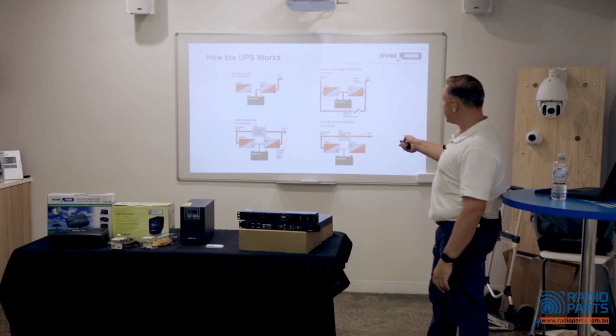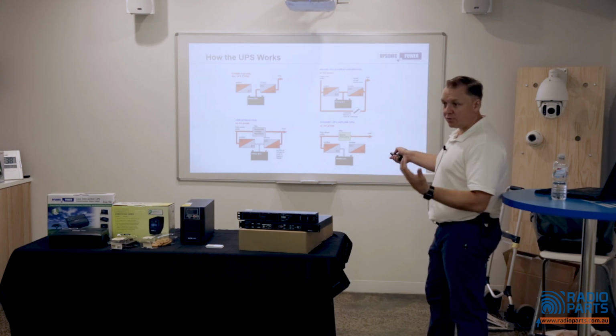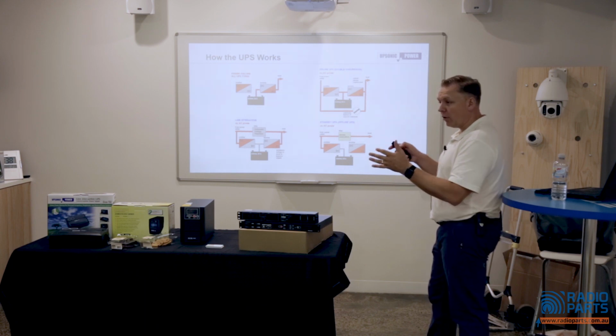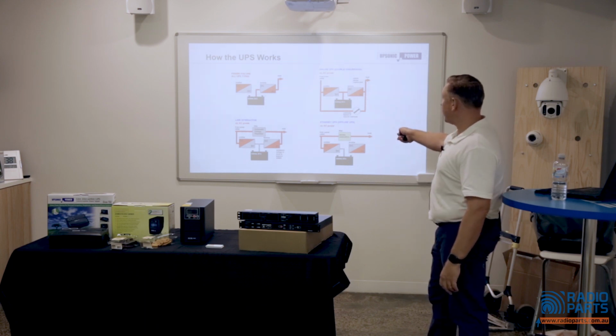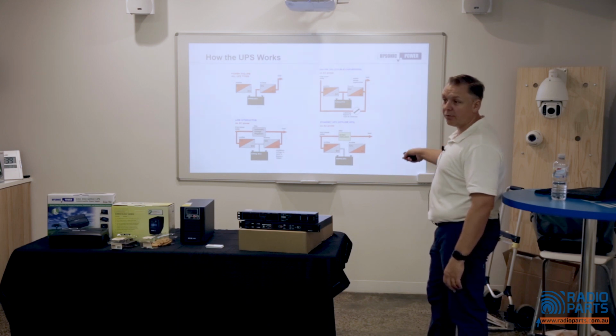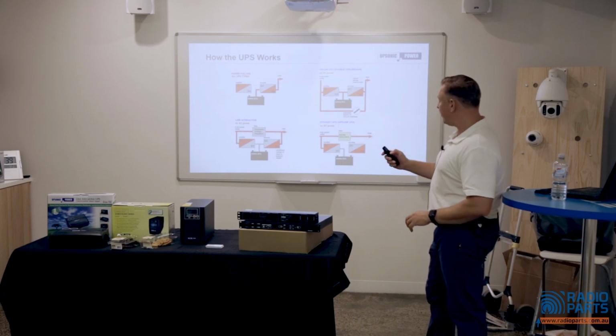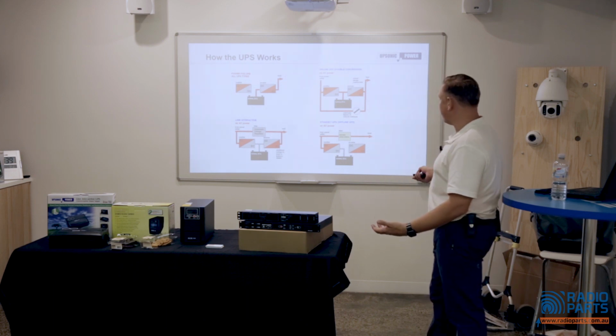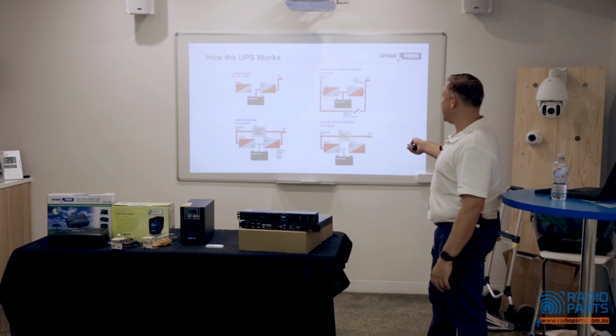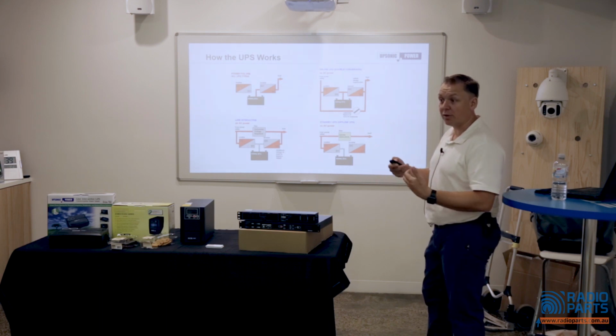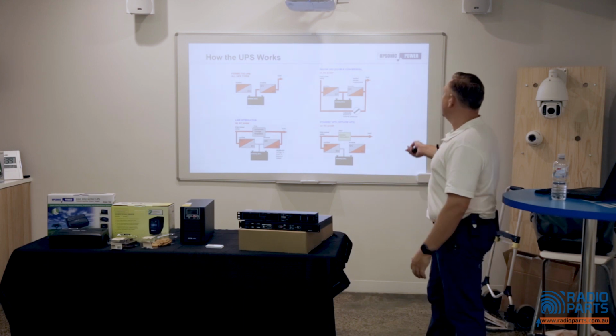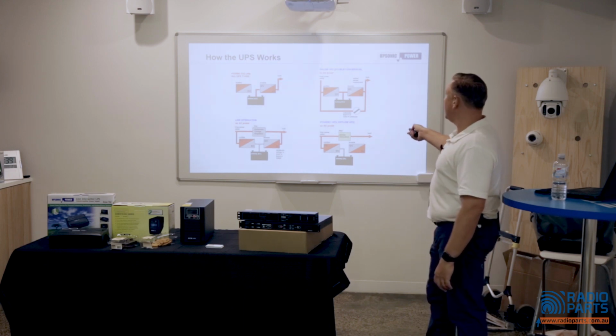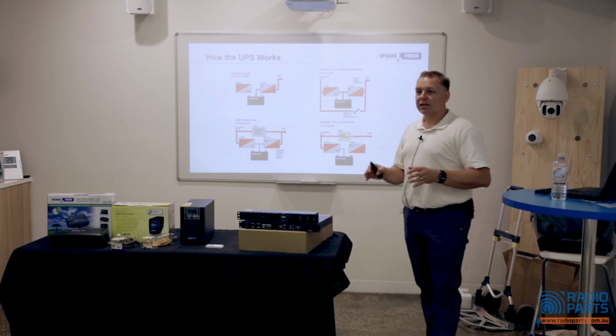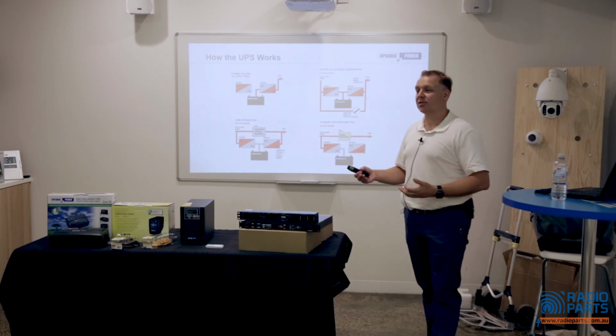With a dual conversion UPS, one of the reasons we use that dual conversion term is that in normal operating mode, it's taking the supply coming in from outside, changing it to DC, charging the batteries and supplying the inverter under normal operating conditions. If you need to manually work on it for bigger units, or if there's a fault, it has a small automatic transfer switch so it can go into internal bypass if it needs to, to maintain continuity to the load. But under normal running conditions, it is always filtering the supply, so you get a better, more consistent load constantly.